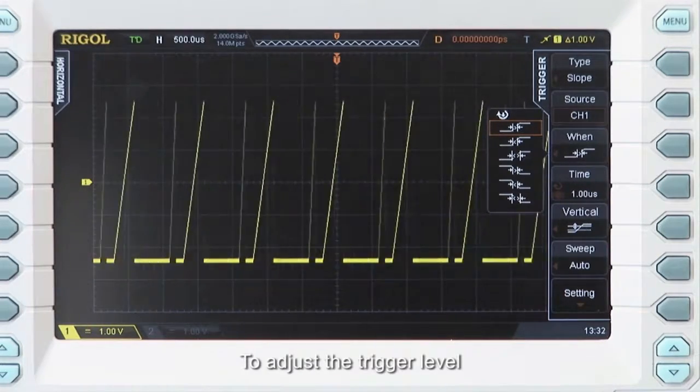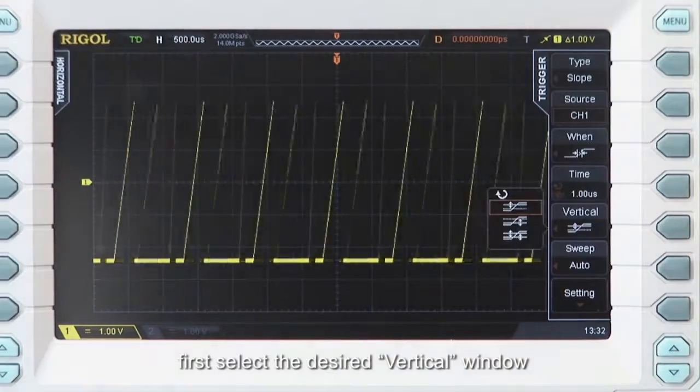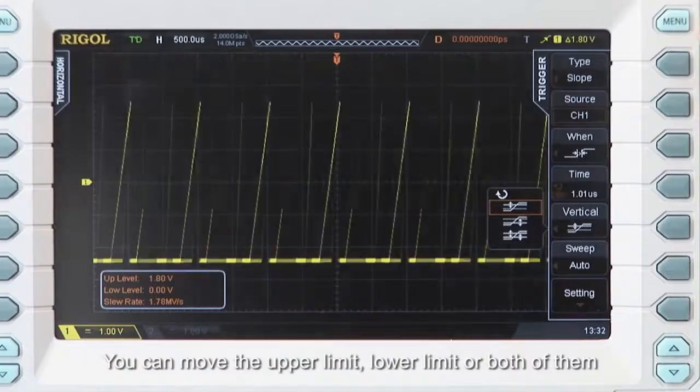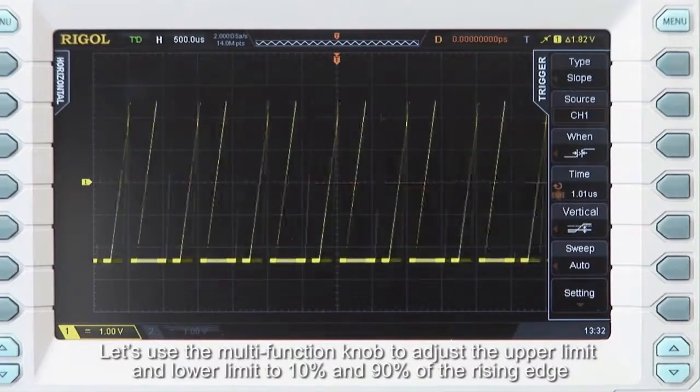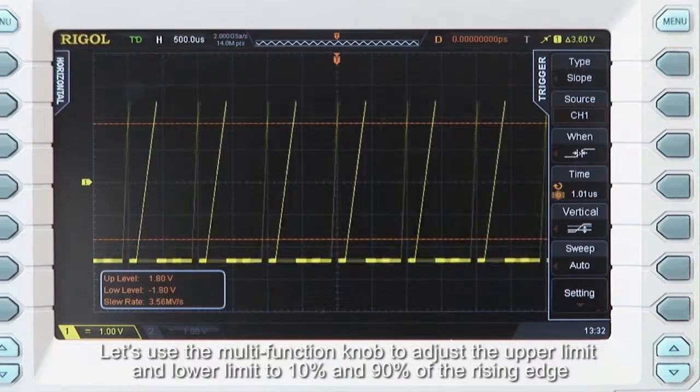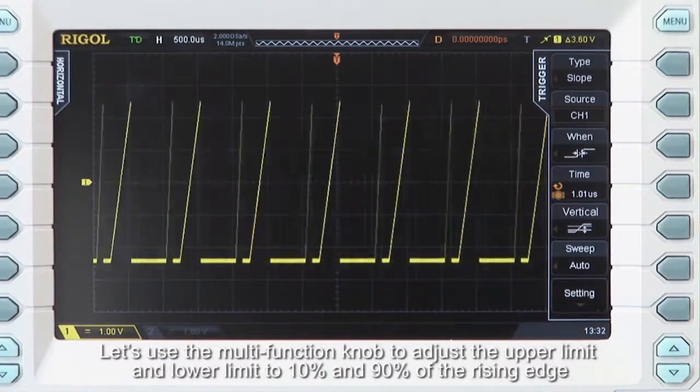To adjust the trigger level, first select the desired vertical window. Then you can move the upper or lower limits, or both of them. Now let's use the multifunction knob to adjust the upper limit and lower limit to 10% and 90% of the rising edge.